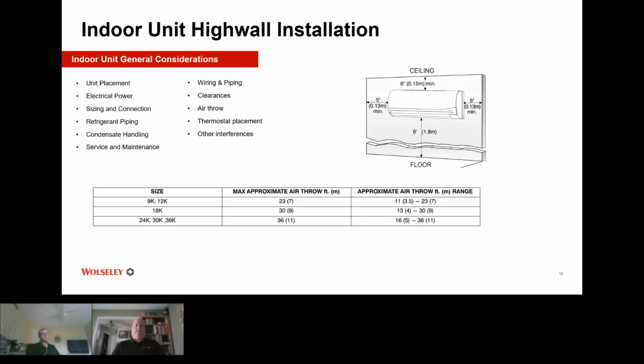Looking for a place to put your high wall unit? It's very important you place it in the proper place to get it to work properly and get the performance that you want out of it. Your electrical power, I mean, you're going to have to drill a hole through the wall too, so make sure you know where you want it. Sizing, connection, refrigerant piping all have to be brought through that hole.